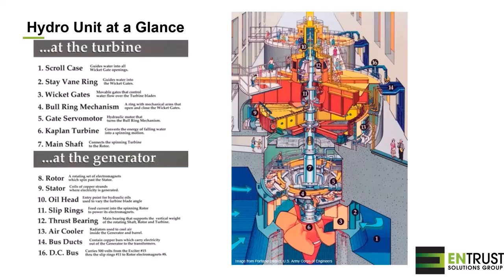On it, we will find a north and a south pole on the periphery with salient poles, and these poles are being operated, if we can say, by a DC current. We need a certain set of DC current to operate a hydro plant. So this energy can be found from batteries, for example, to generate this DC current. And when the DC current passes in front of the stator, number 9, it will generate electricity on the AC with a low voltage. So the voltage will have to be raised by going through the transformer eventually.